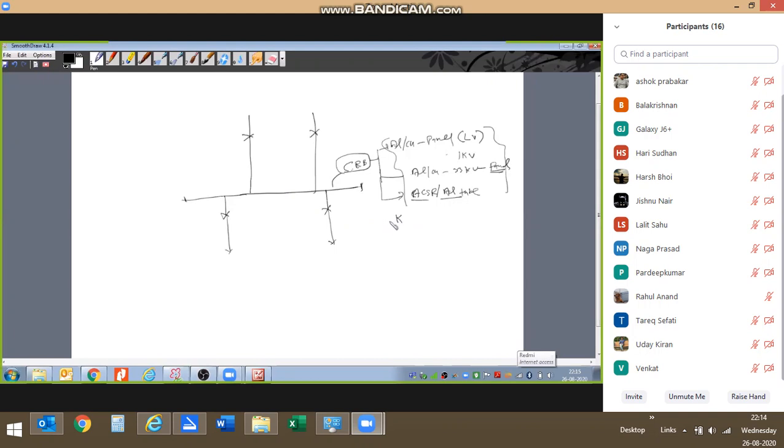So if you remember, we have discussed this bus bar sizing calculations. We have taken all the incomer current, how much current comes in, and that will be equal to all the outgoing current also. But the bus bar capacity should be equal to all the incomer current, and the outgoing can take at maximum that current. Like 200 coming from here, and 200 can go from this; like 400 coming, then 400 might go.